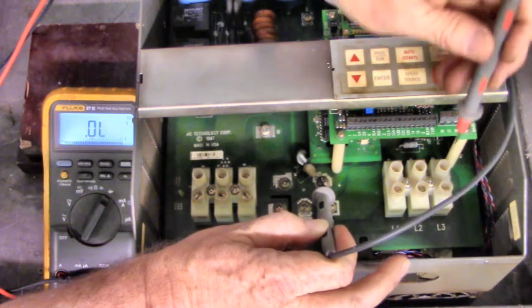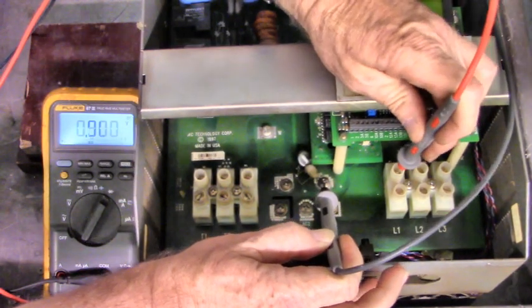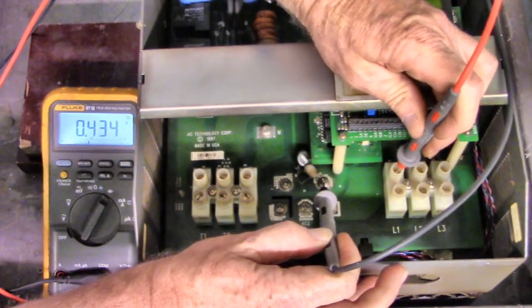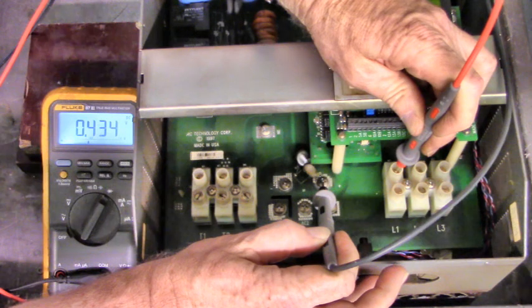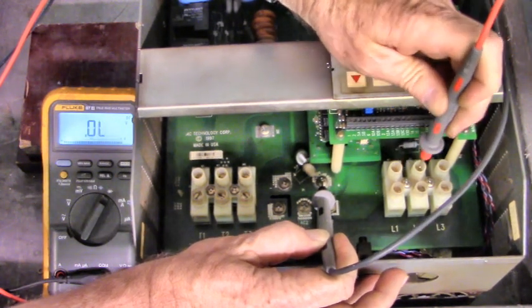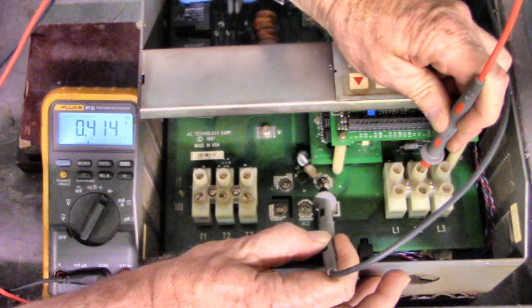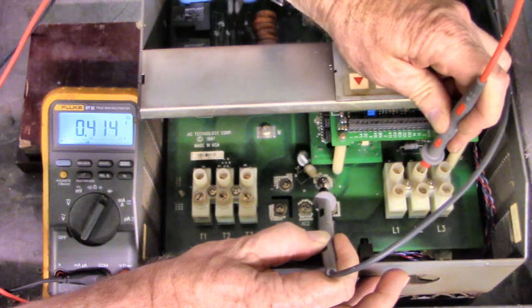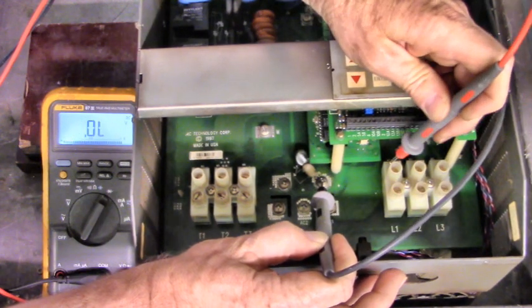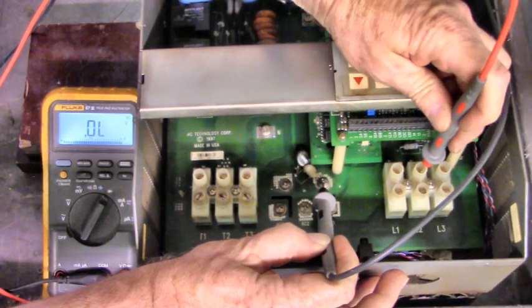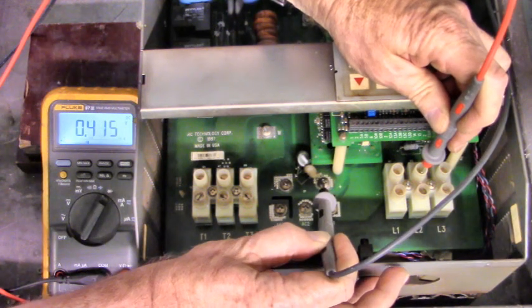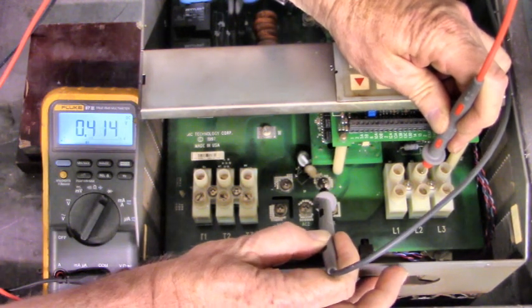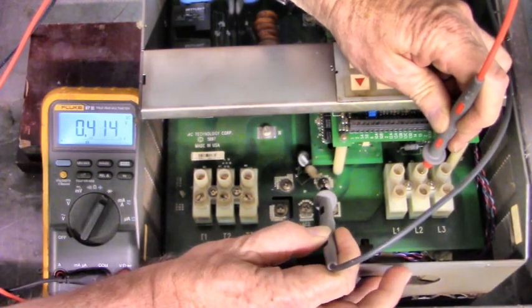Let's put our black lead on three-phase bridge plus, and we'll go to L1. There's a good diode drop of .434. Here's L2 with the red lead, red lead on L1, L2, and L3. Black lead on three-phase bridge plus.